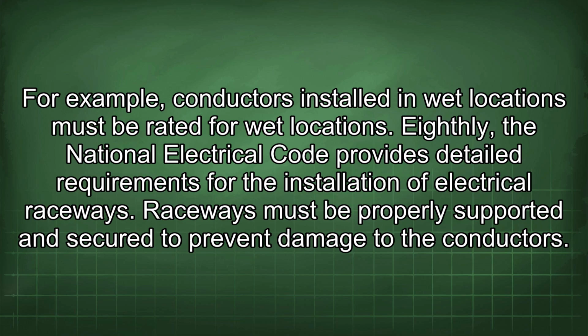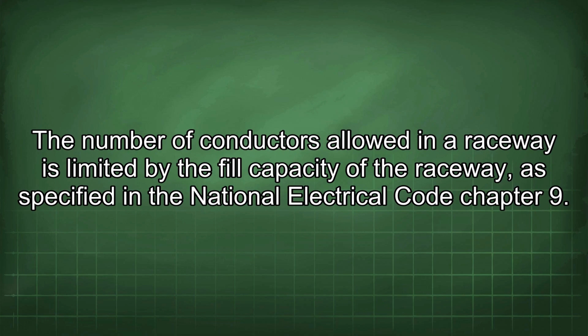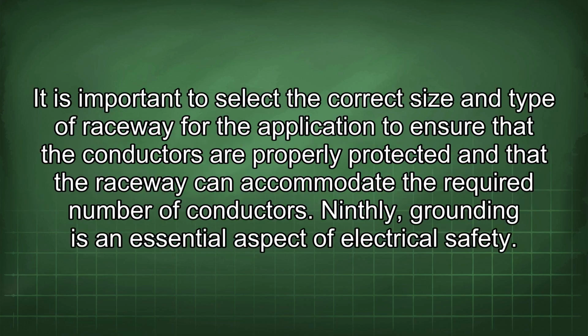Eighthly, the National Electrical Code provides detailed requirements for the installation of electrical raceways. Raceways must be properly supported and secured to prevent damage to the conductors. The number of conductors allowed in a raceway is limited by the fill capacity of the raceway, as specified in the National Electrical Code Chapter 9. It is important to select the correct size and type of raceway for the application to ensure that the conductors are properly protected and that the raceway can accommodate the required number of conductors.